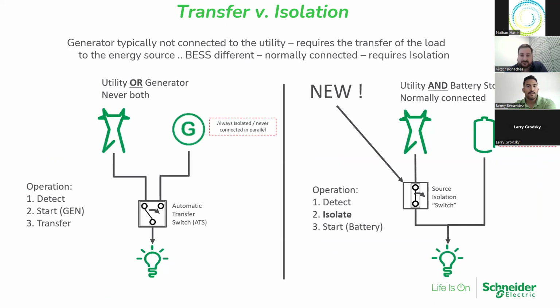So, next slide. Yeah, so we look at transfer versus isolation. I like to show this slide because it distinguishes the two. We look at an automatic transfer switch. Transfer switches select between utility or generator. It's never both. What we mean by that is the generator is almost never in parallel with the utility, unless there's a soft load transfer or CHP unit. But primarily with an ATS, it detects utility, an acceptable source, voltage, and frequency. Once we detect that there's been a change or a dropout, that ATS will send a start signal to the generator. Keep in mind source one is lost, there's no power, and then it sends a start signal to the generator. The generator comes online, and then with generator power on source 2, the ATS energizes the contactor within the switch to initiate transfer. That's the key distinguisher: transferring load.